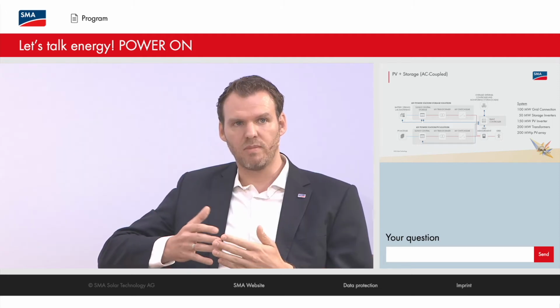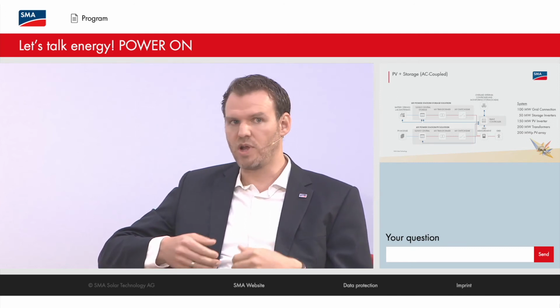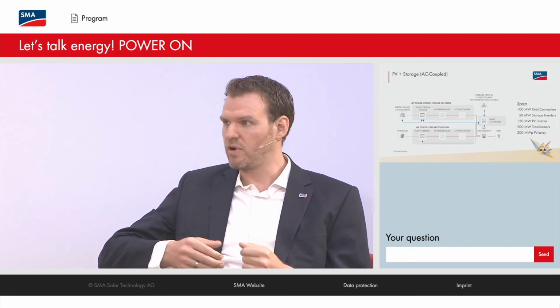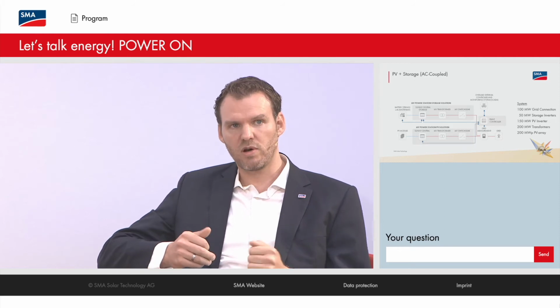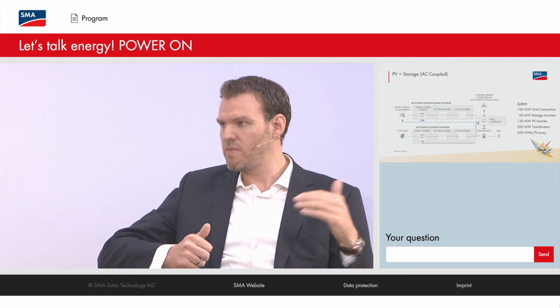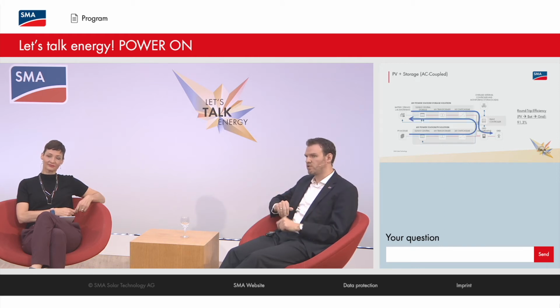So you're basically doubling this up with an AC coupled system. So you have an inverter for the battery, and a transformer and a switchgear, and you do the same for the PV system. So you basically have 2 times the system. Let's assume you have 100 megawatt of grid connection. You want to add 50 megawatt of storage, and additionally have lots of PV. So what you do, 50 megawatt of storage, you add 150 megawatt of PV, because 100 megawatt goes straight into the network and the other 50 to the storage. And then you need in total 200 megawatt of transformers. And you will oversize the PV array based on the PV inverter, so roughly maybe 200 megawatt peak. So that's a DC-AC ratio of 130%, quite commonly done today.